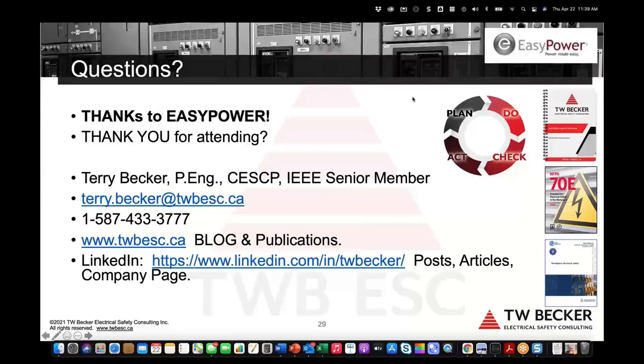All voltage levels. So 70E and Z462, low and high voltage electrical equipment, right? So low and high voltage definitions, US, 1,000 volts or less for low, 1,001 volts or higher for high. In Canada, we have actually just moved in our latest edition of the CE Code Part 1 to the same voltage levels for defining low and high voltage. So 70E and Z462 apply to enclosed electrical equipment up to 35 kV or higher these days.